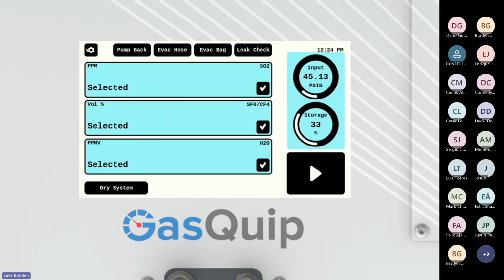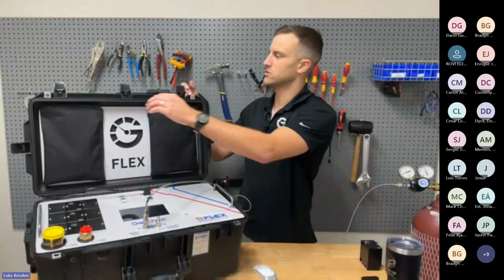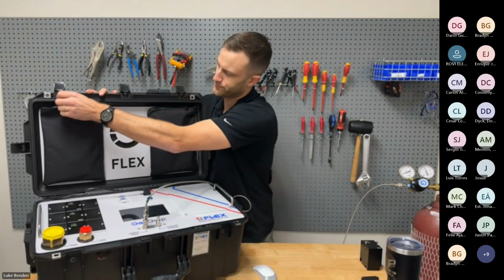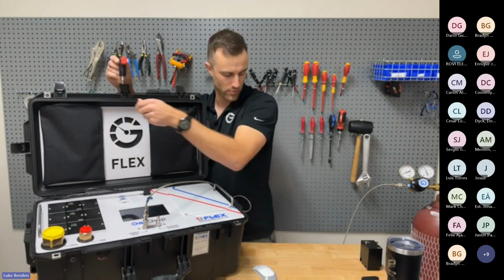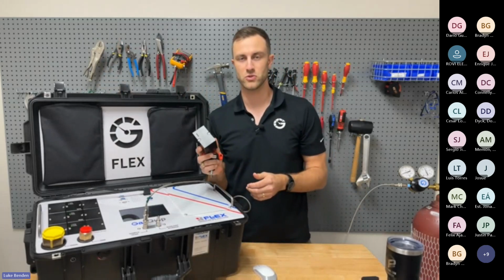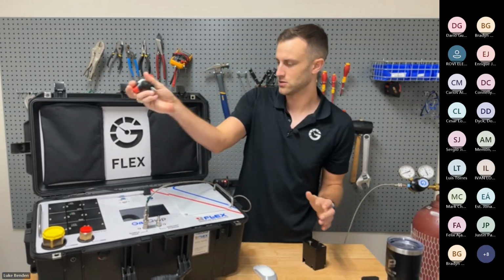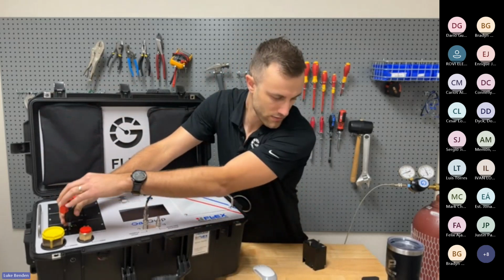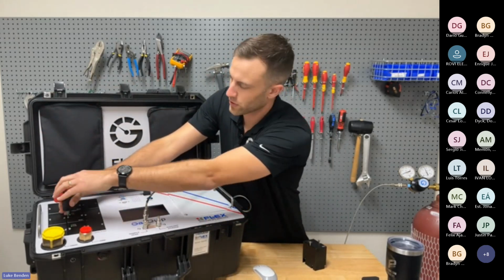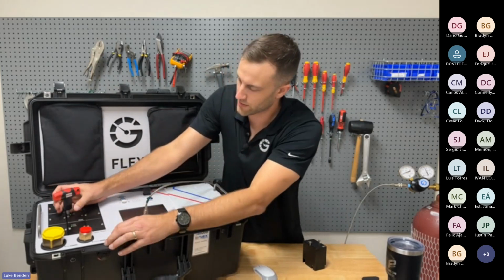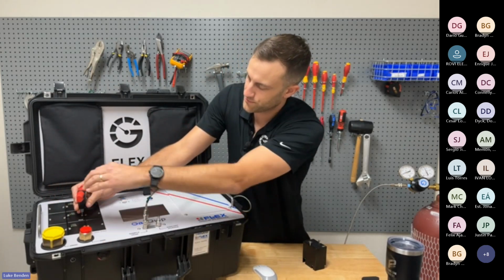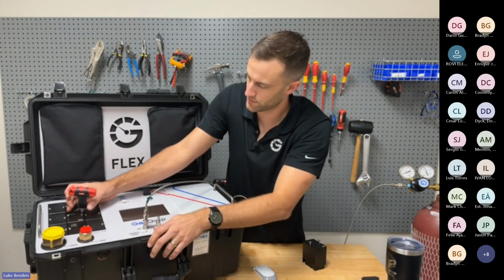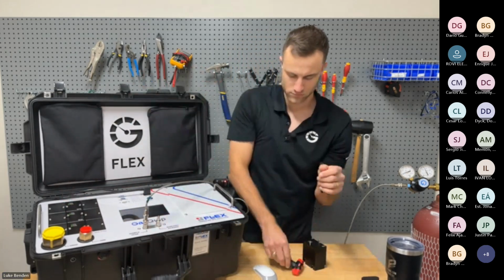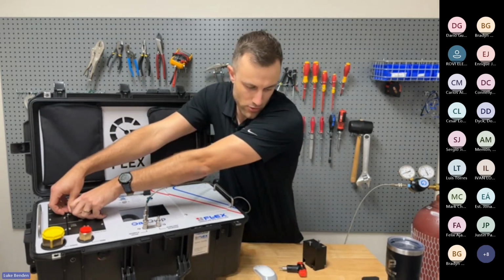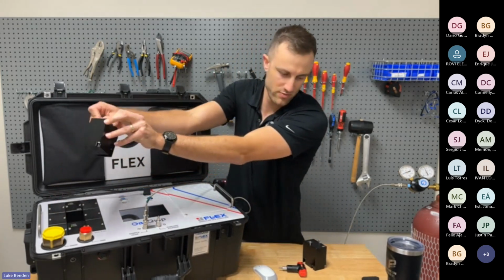We can talk about calibration for a sec, and I'll do a little demo of how to do that. So if we go into our bag up top here, we got our torque wrench. So basically we would send you whatever sensor module is due to be replaced, and you would take your torque wrench and see this. Let's do this top one so you can see it. Take your torque wrench. There's two long bolts on either side of each sensor module. You're going to unscrew those like so. And pull that up like that, and it just slips out like this.